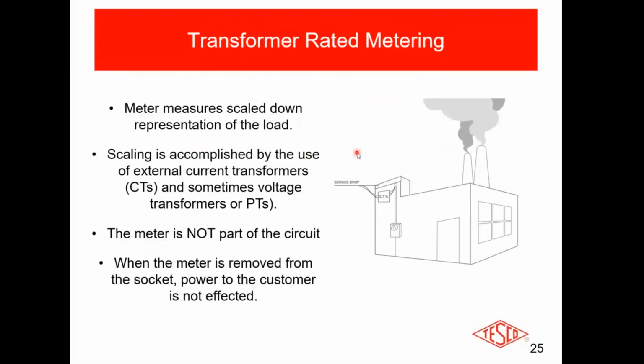So the meters in a transformer-rated service typically cannot possibly handle the amount of current that is coming into the facility. This is usually your commercial and your industrial facilities. You're bringing in a lot more power than the meter can possibly handle. So what we did, going all the way back to the 1890s, is we scaled the meter. The meter is basically just a scaled down representation of the load. So if you've got CTs in there that are 400 to 5, that means for every 400 amps coming into the building, the meter only has to see 5.